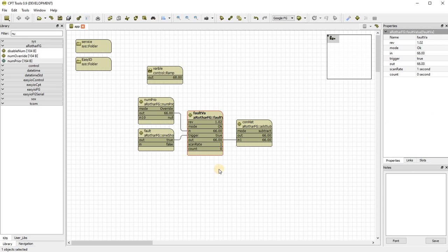So this way it helps you track down the fault, and it will only log when there's an event. So what you'll see is this, it'd be better if I could spell, wouldn't it? So this COV history will record the value on the receipt of the fault trigger. So when it clears, it won't change.